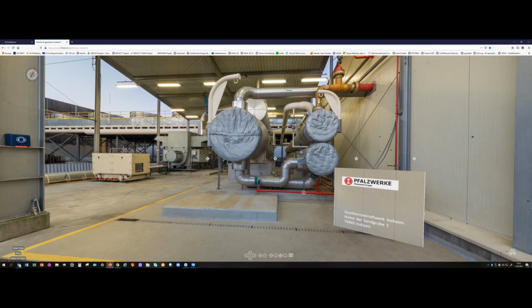Did you already face pollution in the isopentane, and if yes, what were the reasons? So far not. In the past, we had a very slight leakage in one of the pipes of our vaporizer. We have tube and shell heat exchangers, probably it was a material problem a couple of years ago. We had a slight leakage in one of the tubes, and therefore a slight water introduction into the isopentane, but this has already been limited by exchanging the isopentane and cleaning it. So we do not have any pollution of the isopentane so far.